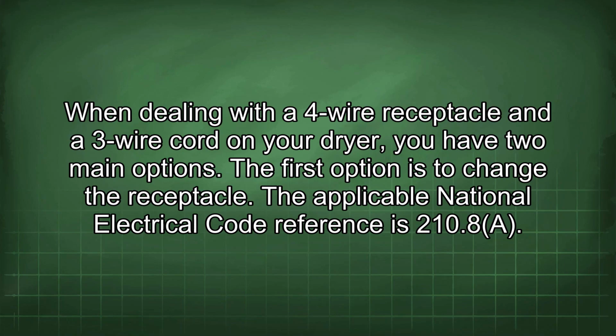When dealing with a 4-wire receptacle and a 3-wire cord on your dryer, you have two main options. The first option is to change the receptacle. The applicable National Electrical Code reference is 210.8a.